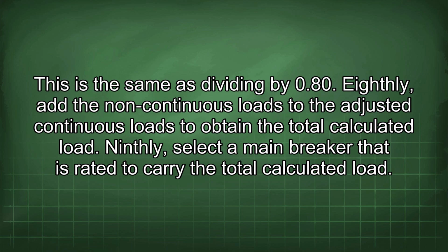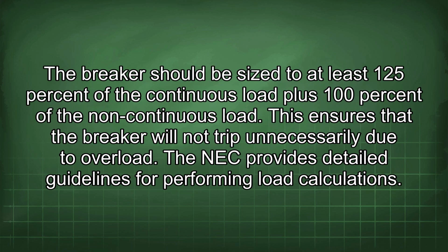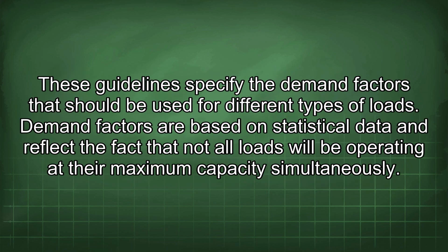Ninthly, select a main breaker that is rated to carry the total calculated load. The breaker should be sized to at least 125% of the continuous load plus 100% of the non-continuous load. This ensures that the breaker will not trip unnecessarily due to overload. The NEC provides detailed guidelines for performing load calculations. These guidelines specify the demand factors that should be used for different types of loads.